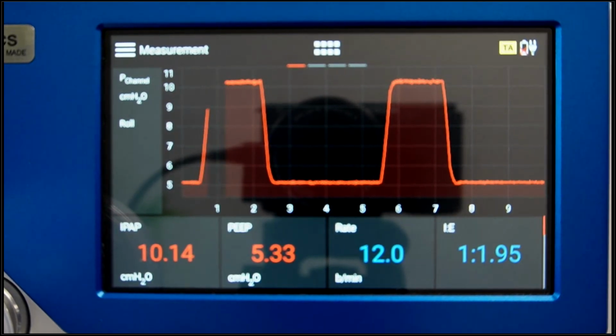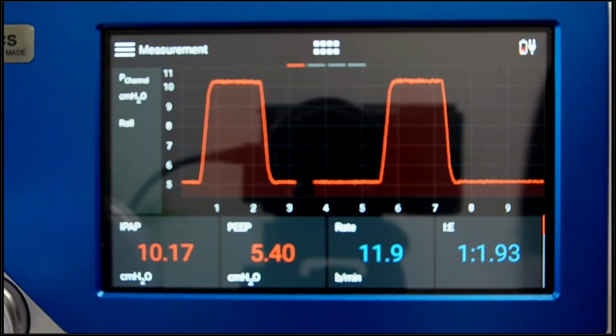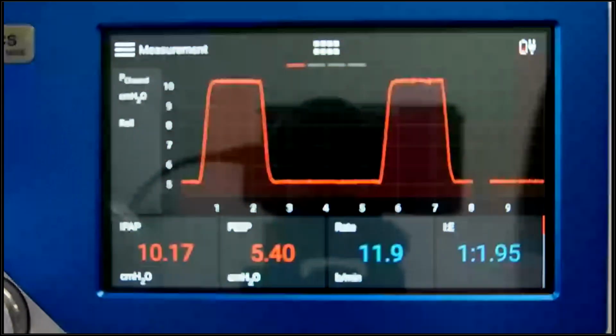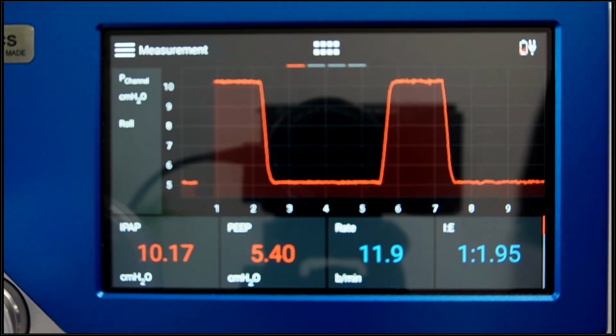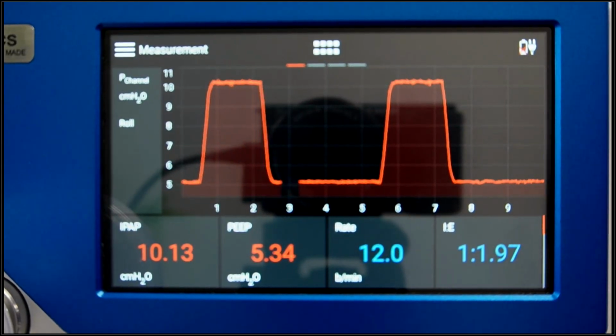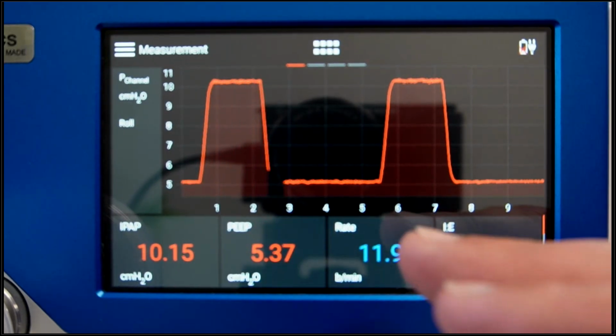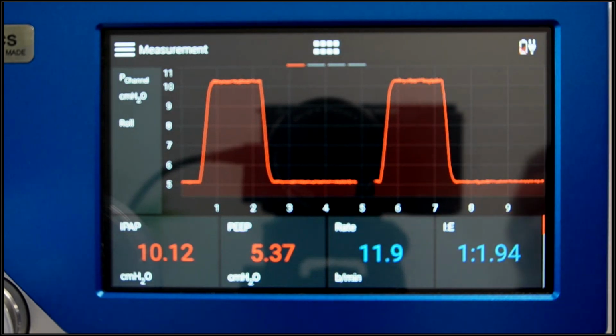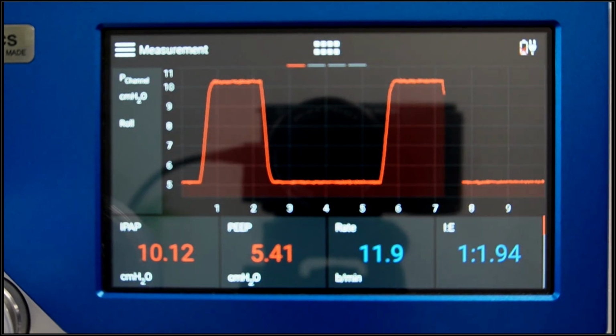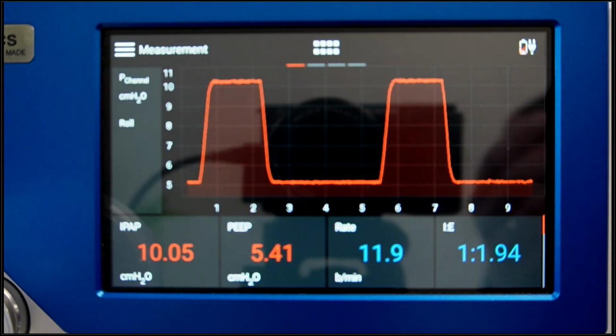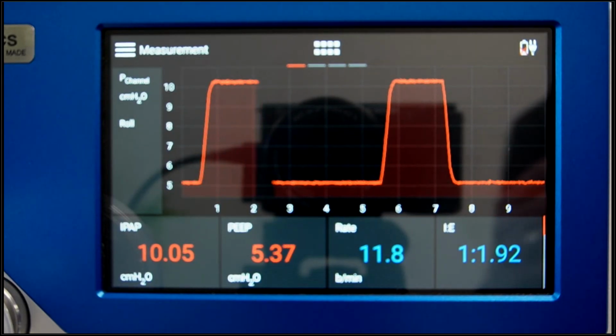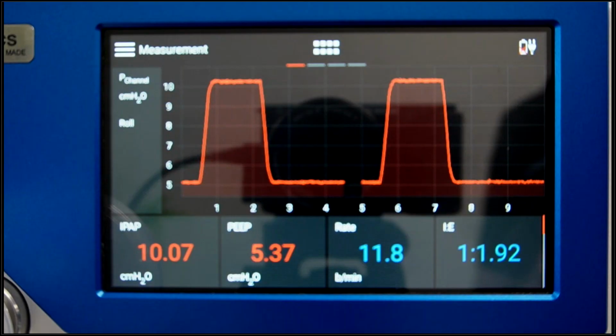So on modern gas flow analyzers like our Citrex H5 or this here, the Flow Analyzer Pro, you can create profiles and save all the critical settings that we've discussed earlier in a profile for later use. So your gas type, your gas standard, your trigger settings, and all kind of screen customization. So on most gas flow analyzers, I can customize exactly what I want to see on my screen. Here, even I can customize the color of my measurements, which is sometimes very helpful to find the value I'm looking at quicker.